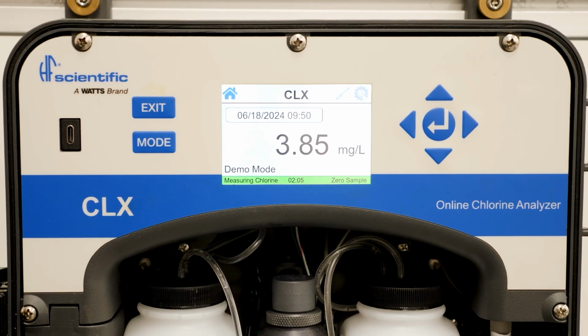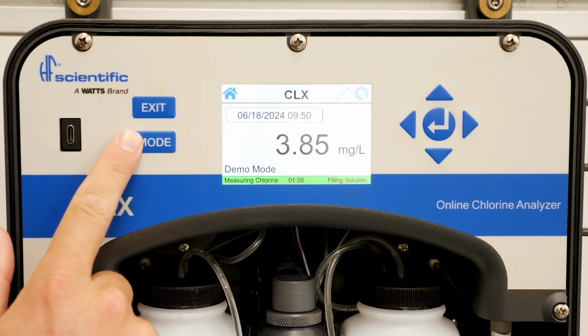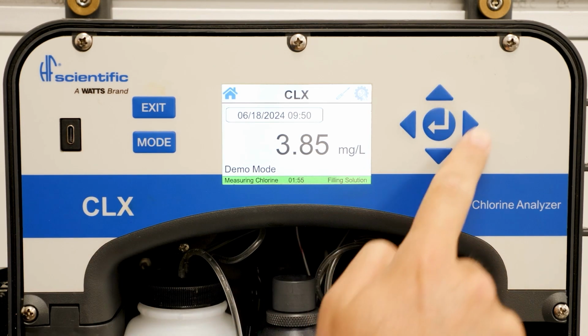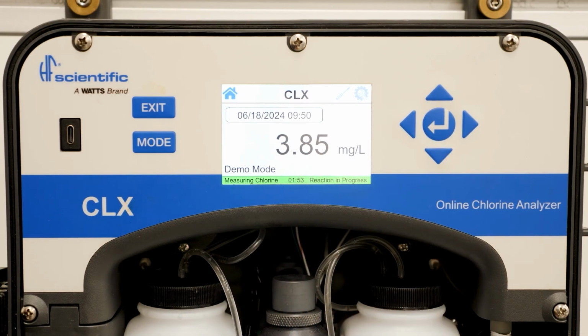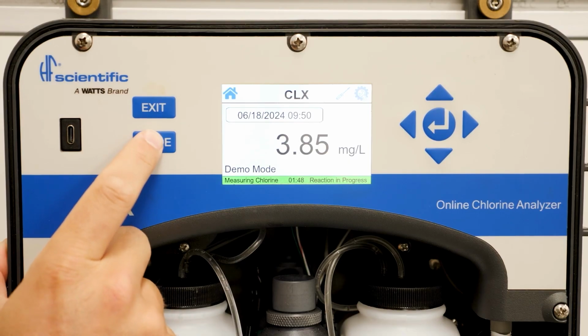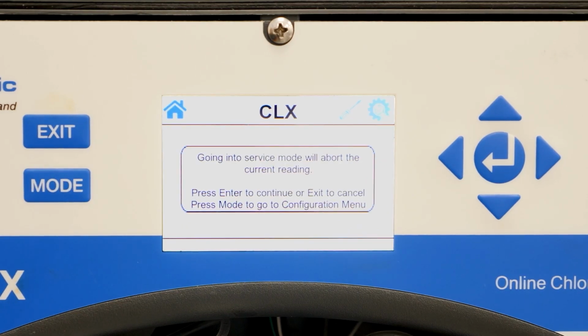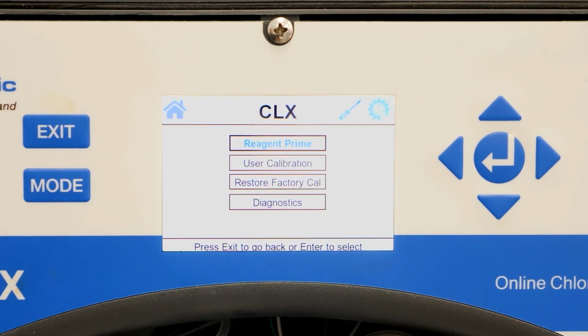The buttons on the CLX update are also different from the previous version. You will see the new version features an exit button, a mode button, 4 direction buttons, and the enter button. Pressing the mode button will bring up a prompt asking if you want to go into the service menu. Press enter to go into the service menu. This will stop and drain the analyzer, allowing you to change reagents, flush reagent lines, change tubing, or perform other maintenance with no water going through the analyzer.